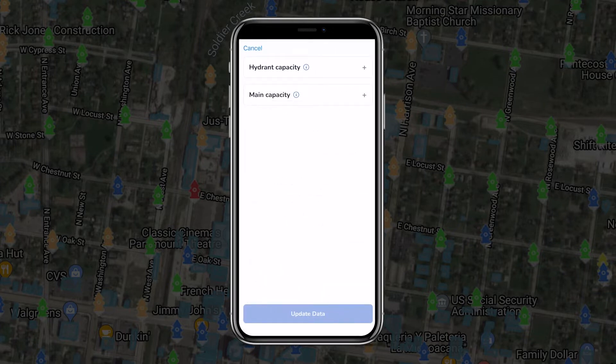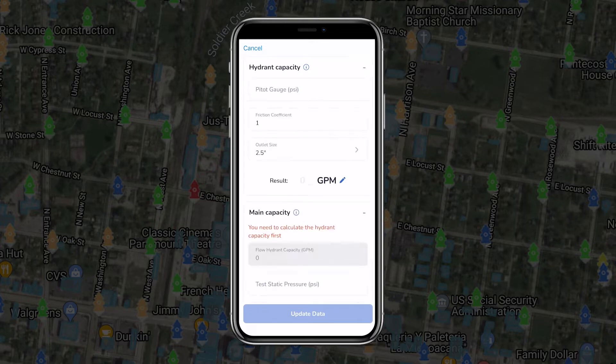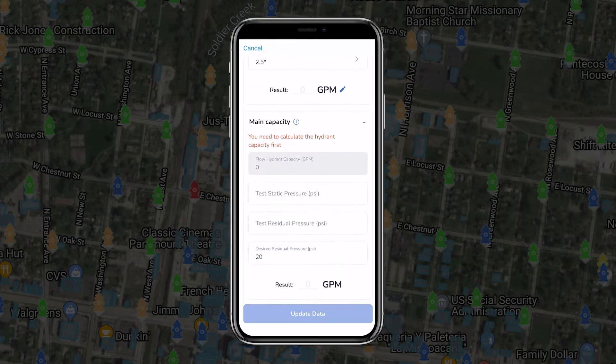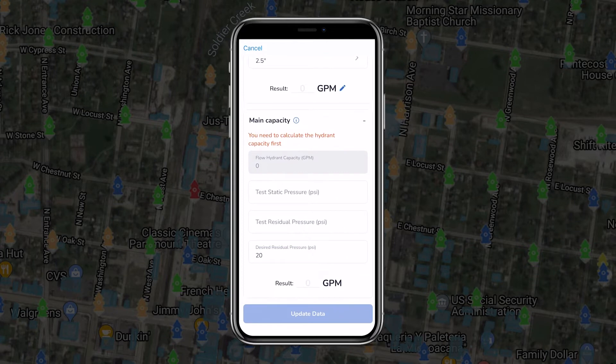To begin a two-hydrant test, one team member will attach the cap gauge to the test hydrant for measuring static and residual pressure. They'll open the hydrant valve and then use the cap gauge valve to vent air or other contaminants that could affect readings.